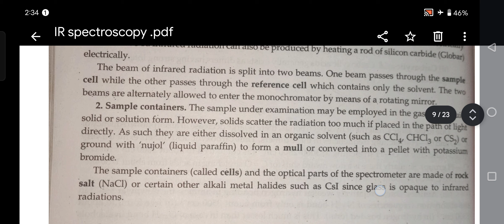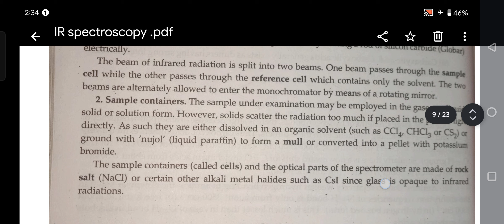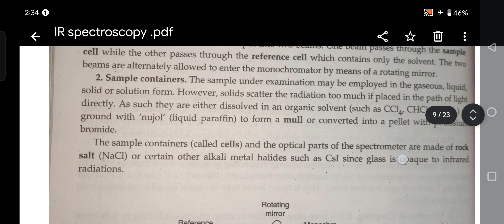The beam of infrared radiation is split into two beams. One beam passes through the sample cell, while the other passes through the reference cell, which contains only the solvent. The two beams are alternately allowed to enter the monochromator by means of a rotating mirror. Sample containers. The sample under examination may be employed in the gaseous, liquid, solid, or solution form.